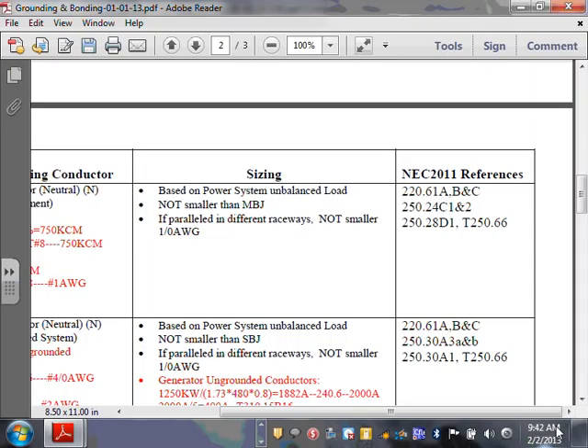Cool. I know engineering firms, guys, they don't go deeper. When I worked for LB Beckett, they really cared little about the supply side bonding jumper for the most part. Main bonding jumper, they don't care too much about the equipment bonding jumper on the load side, at least our firm. I don't know if anybody works for an engineering firm. Do you guys size the equipment bonding jumper on the supply side and the equipment on the load side? Engineering firms typically depend on the electrician or contractor to size them, unless you're a contractor who has engineers in house. They depend on you to size the equipment bonding jumper on the load side.